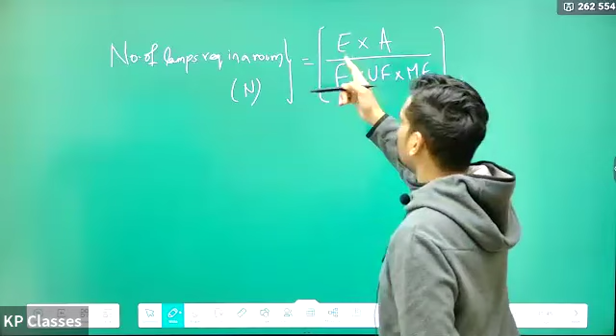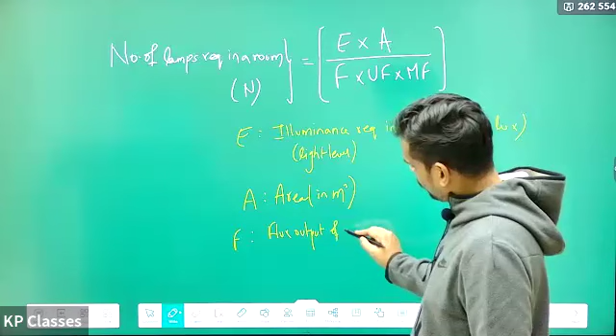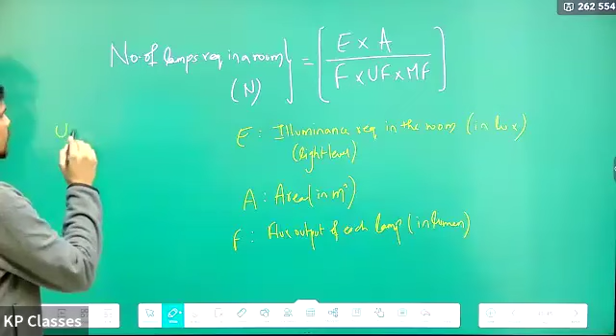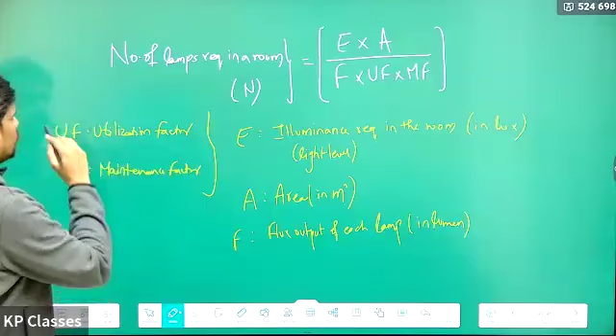This is also called the light level. Light level required in the room. This is measured in lux, multiplied by the area. This is called the surface area in square meter, divided by F, here F is the flux output of one lamp. This is in lumen. Flux output of one lamp in lumen multiplied by the utilization and maintenance factor. In this, there are two factors we use. UF stands for utilization factor. MF stands for maintenance factor. We multiply the flux with these factors to get the effective flux output.